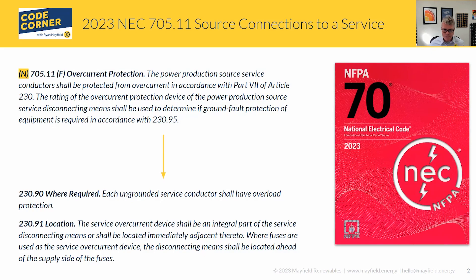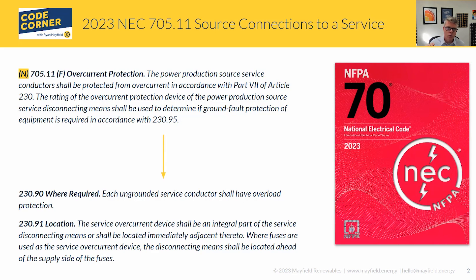I'll show you a picture towards the end. The question that came up originally was: in 2023, 705.11F is overcurrent protection. In 2020, if you're doing a compare and contrast, that was in subsection C — still overcurrent protection but in subsection C. And that's where we found the limitation of 10 feet or 70 feet, depending on commercial versus residential applications. In 2023 it gets moved to F.